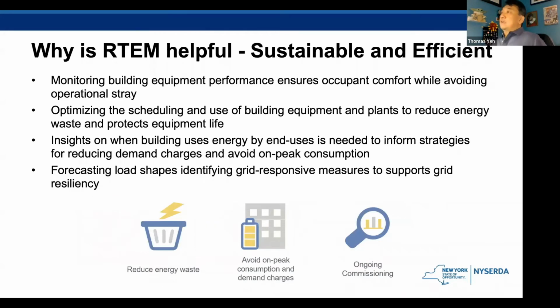Another benefit of RTEM is optimizing the schedule of large mechanical equipment that uses a lot of energy. Just this one measure could make a big difference in the property's sustainability and efficiency. For instance, if a central plant operates 12 hours a day, reducing just 1 hour from the schedule saves over 8% of energy and reduces the equipment's wear and tear.